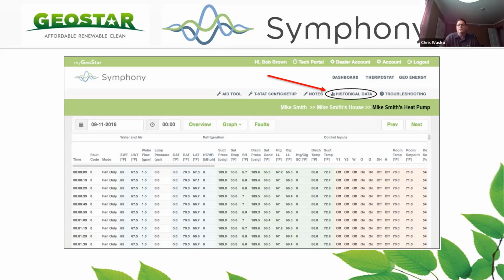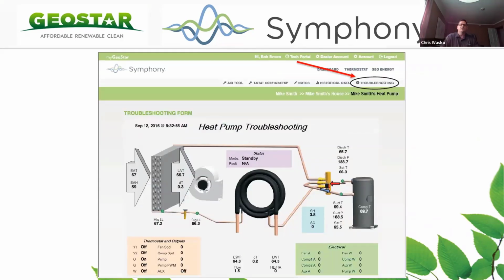And we're going to show you some of that as we go along into the preview. It also gives you a troubleshooting heat pump chart, where it puts the inputs of what's going on in the system currently, so you can see in real time how that unit is operating. You may be able to say, here's where we may have a problem, when you're looking at the temperature ranges, seeing where the discharge temperature is versus the latent temperatures and what's going on with the airflow across the coil. Maybe we don't have enough airflow and it shows up in the temperature difference, which could easily be a dirty filter, which can save you a trip and the homeowner a lot of money.